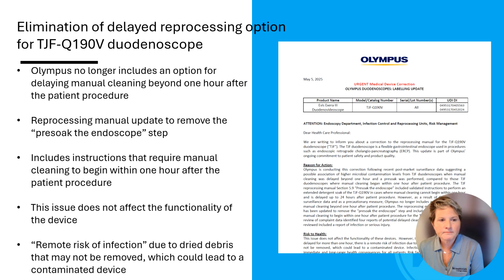And then Olympus no longer includes the option for delayed manual cleaning beyond 1 hour after the patient procedure. Reprocessing manual update to remove the pre-soak from the endoscope. That step is completely removed. And it includes instructions that require manual cleaning to begin within 1 hour after the patient procedure. And they stated that this issue does not affect the functionality of the device at all. And they also acknowledge that there's a remote risk of infection due to dried debris that may not be fully removed, which could lead to a contaminated device.